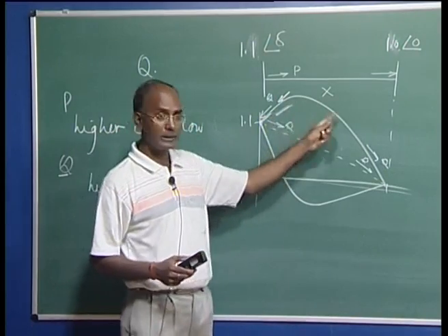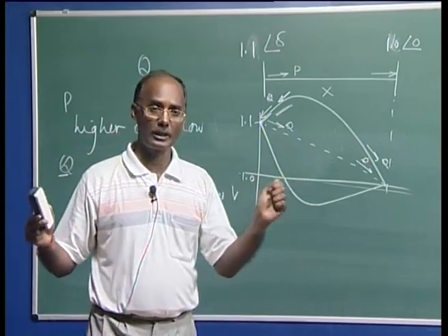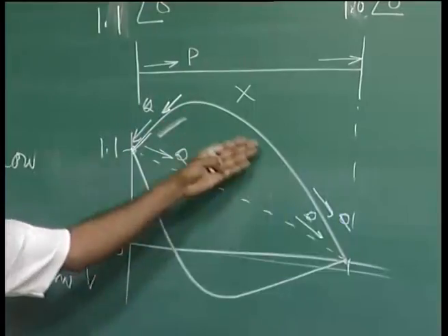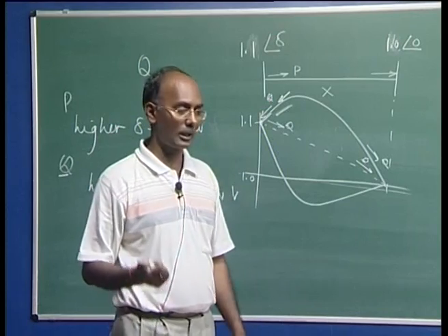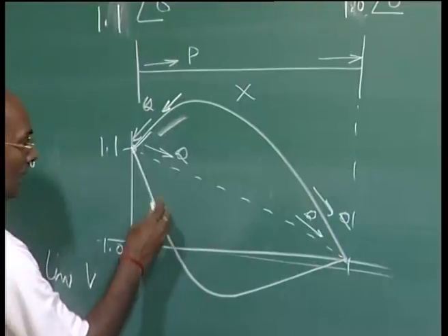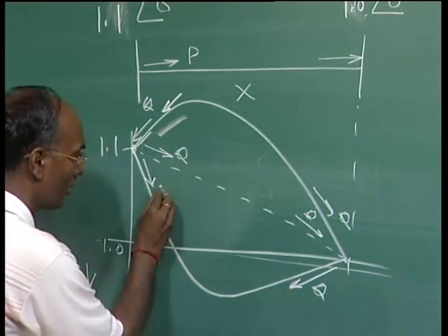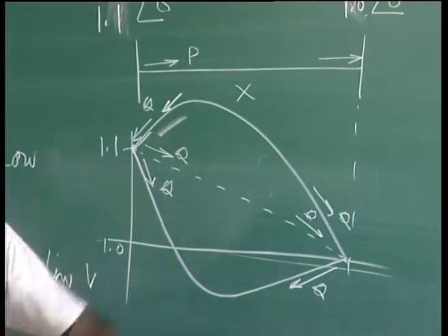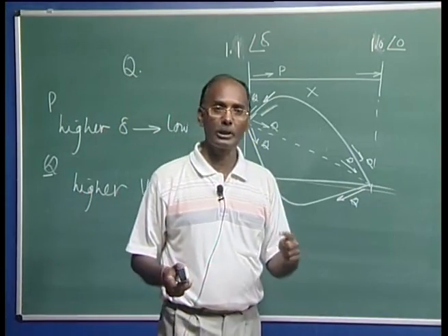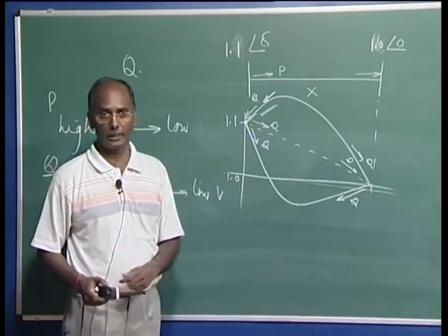And this voltage profile is coming due to the distributed parameter, the charging of the transmission line. If the transmission line is long and lightly loaded, we can end up with this scenario. Similarly, if the line is highly loaded, meaning more current flowing in the line, this scenario may arise, and you can see the reactive power is flowing here, and here also reactive power is flowing. So the Q here, we cannot say it is unidirectional. However, the P is unidirectional. Q can flow in either direction. All the four possibilities are there.